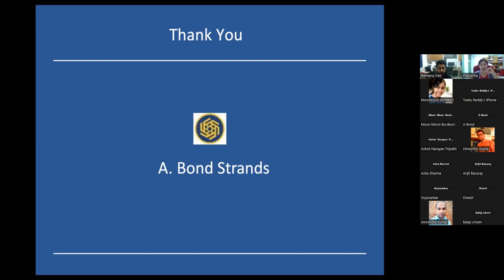Sir, one question out of curiosity. You said that in IIT Powai you installed the insulators. What was the insulator material there? We installed our insulators in our switches. We made a product, switch fuse units, and these panels were placed wherever there was a transformer, to control the transformer, in various substations throughout the campus. The epoxy went into the switchgear. Of course, it was epoxy based. It was basically an indoor application. The panels were kept inside the substations throughout the campus.